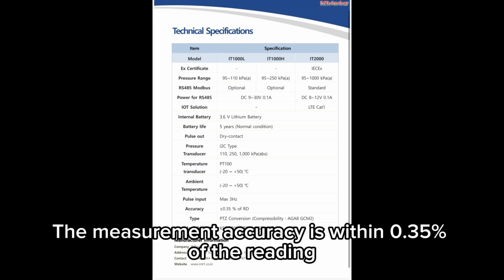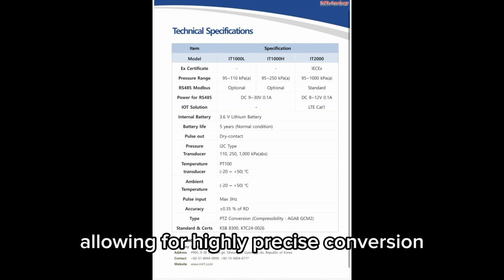The IT1000 uses the PTZ correction method based on the AGA8 GCM2 formula. The measurement accuracy is within 0.35% of the reading, allowing for highly precise conversion.